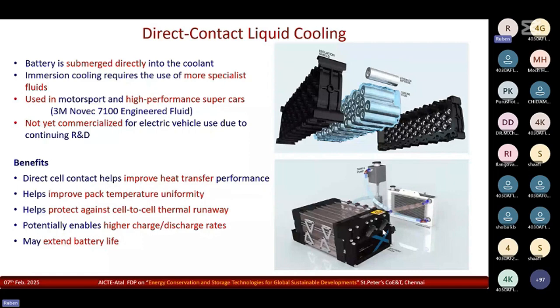The maximum temperature should not exceed 40 degrees centigrade, and on the lower side it should not go below 15 degrees centigrade. There is also a norm generally desired in the industry that the maximum temperature difference within the module, the delta T, should not exceed 5 degrees centigrade. So temperature uniformity is also an important parameter we monitor when thermally managing these batteries, basically to protect against cell-to-cell thermal runaway.